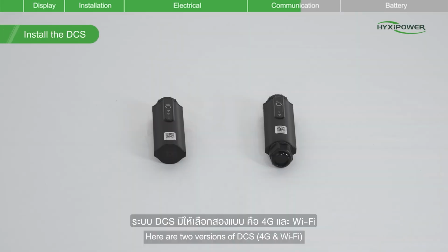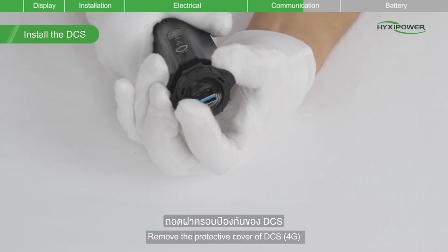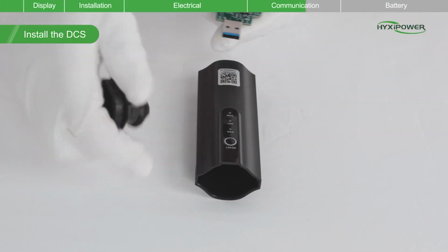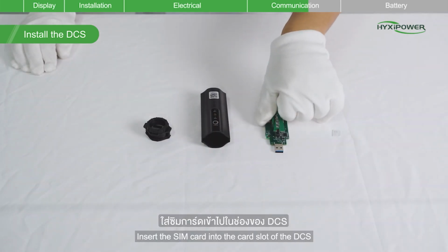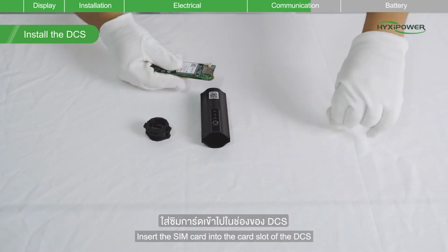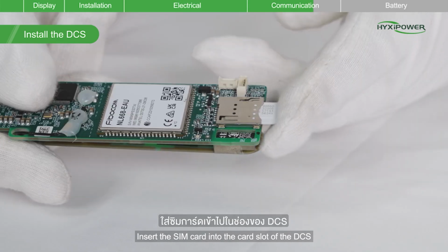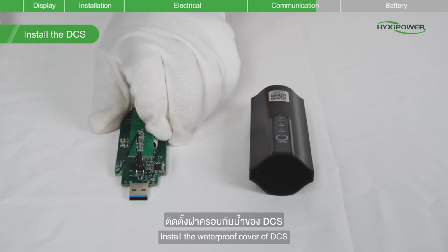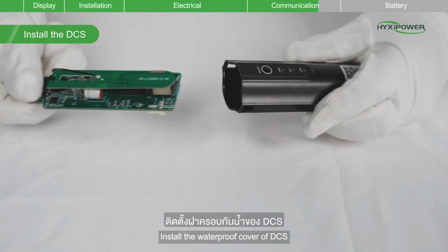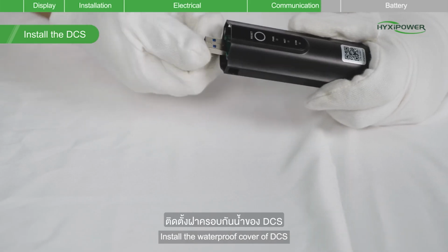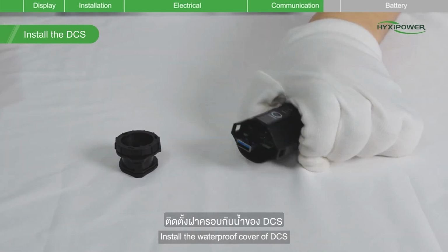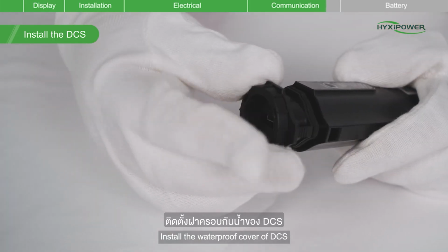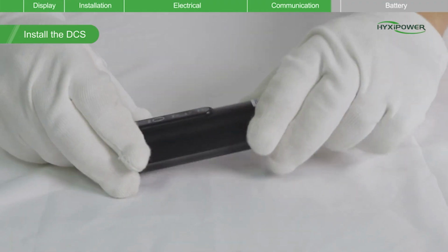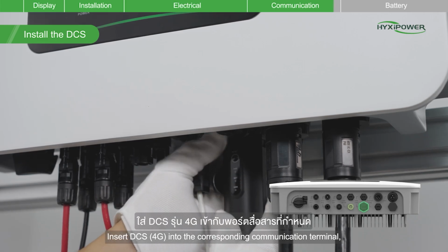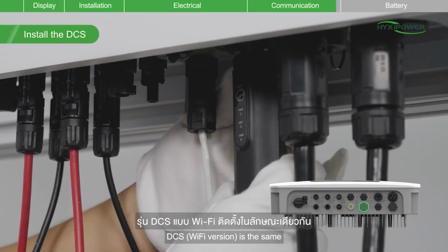Here are two versions of DCS, 4G and Wi-Fi. Remove the protective cover of the DCS. Insert the SIM card into the card slot of the DCS. Install the waterproof cover of the DCS. Insert the DCS 4G into the corresponding communication terminal. The DCS Wi-Fi version is the same.